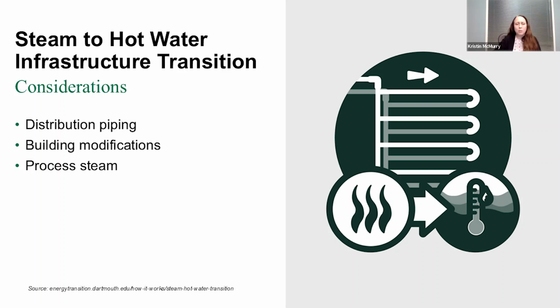A lot of times when we're talking about hot water, we're talking about low temperature hot water. So if the terminal equipment needs 180-degree water, but we're only distributing at 140, you need to make some pretty big changes within the building. That might be the biggest ticket item on your entire project, and the distribution piping is pretty substantial as well.